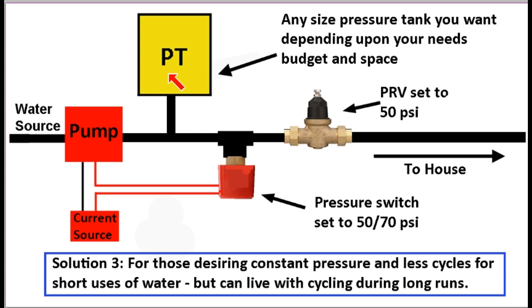Whereas with a cycle stop valve, you need a very small pressure tank, and every time you use water, the pump will go on. Now, cycle stop valve likes to say, oh, there's no reason you can't put a large pressure tank with a cycle stop valve. Oh, yes, there is. There's a very big reason why you can't use a large pressure tank with a cycle stop valve. In fact, two reasons.